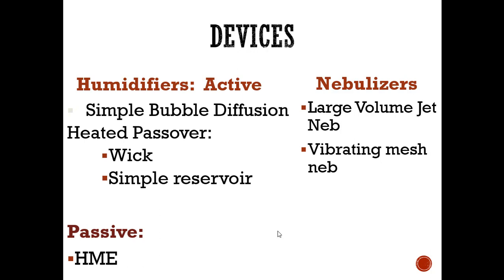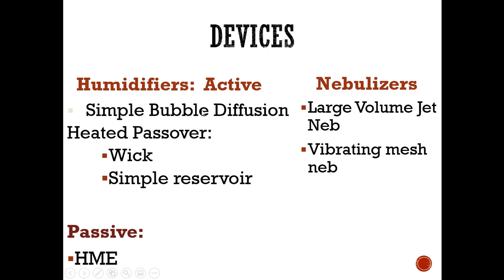Looking at humidity devices: active humidifiers include the simple bubble diffusion device — the bubbler — and the heated passover humidifier, which has two examples you'll learn: the wick and the simple reservoir. There is one passive humidifier — the HME. For nebulizers or aerosol-delivering devices, we focus on the large-volume jet neb and the vibrating mesh neb. For boards, focus primarily on the heated passover wick or simple reservoir, the bubbler, and the large-volume jet neb.